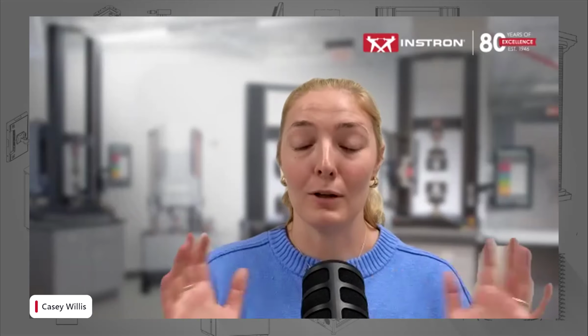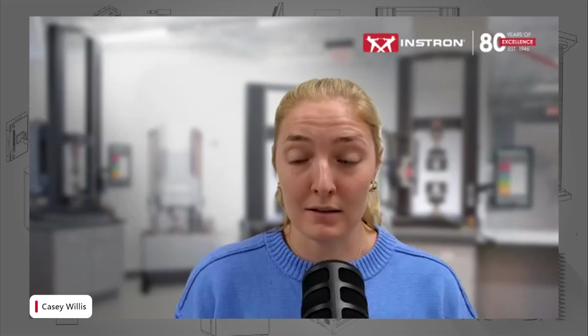Before we jump in, let's just get an understanding of what an extensometer is. A quick little refresh. Extensometers come in all shapes and sizes. They're designed with the same goal in mind, and that is measuring material deformation. The principle of operation for extensometers is pretty simple. You have your initial gauge length set. You can see it in the image above.